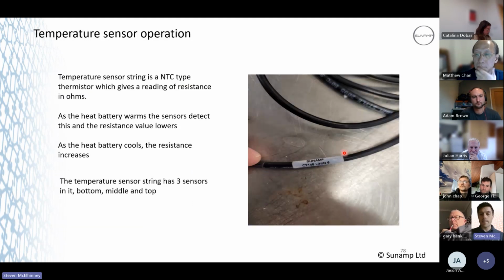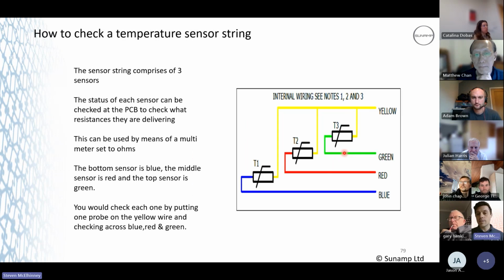Another way to go about it is to check your resistances. You could do your start test. Check yellow across blue, yellow across red, yellow across green, and note down your resistances. Leave it for half an hour while you're tidying up, doing your paperwork or whatever. Go back to it, turn the power off, and check yellow across all your 3 sensors again. See what the difference is. If the resistance on T1 has reduced, you know the heat's going in there.